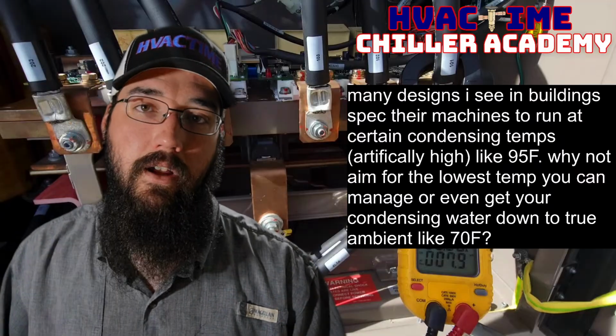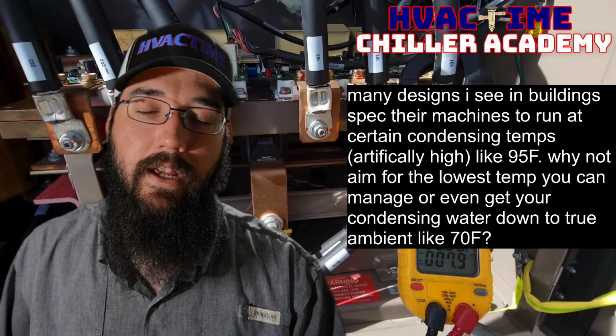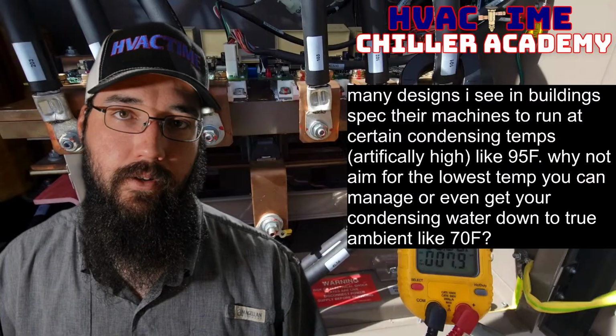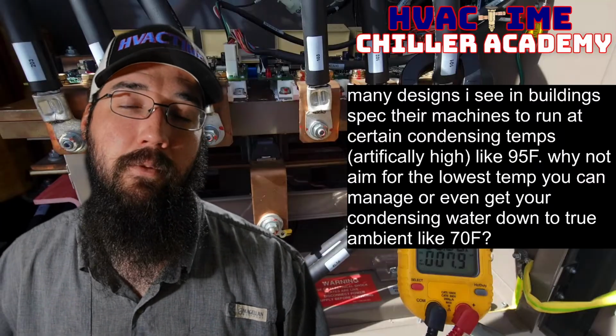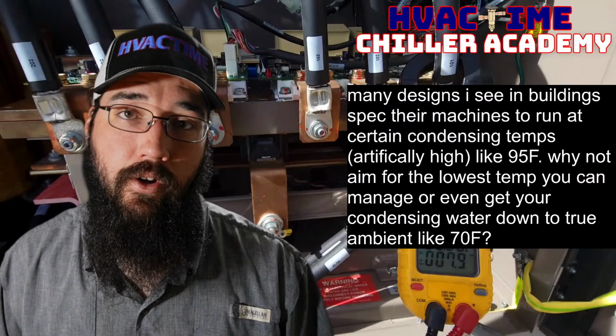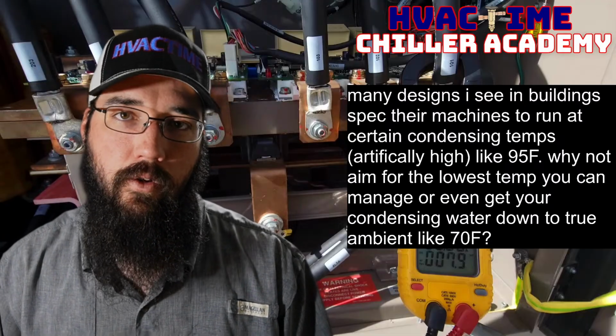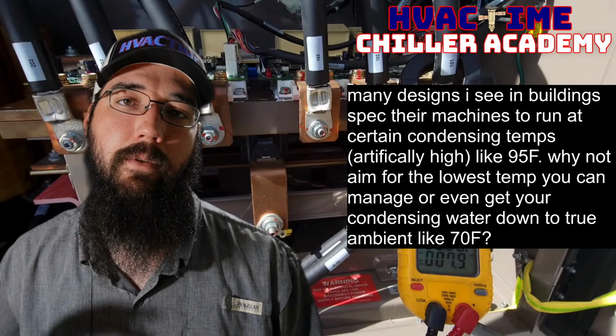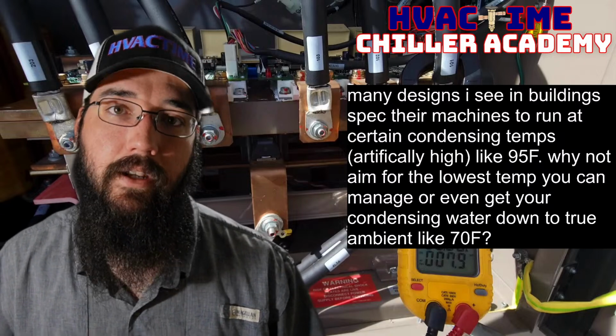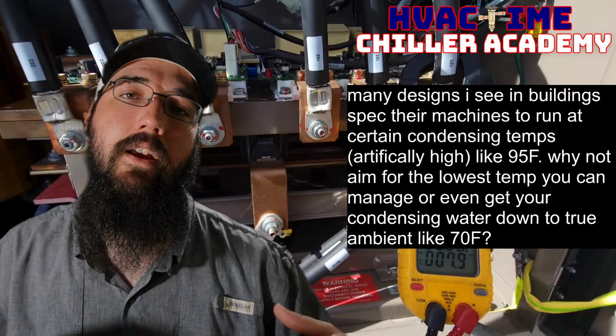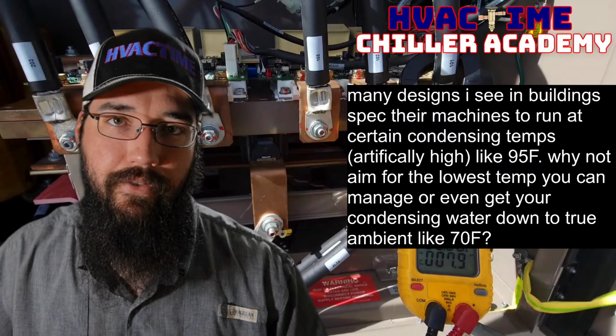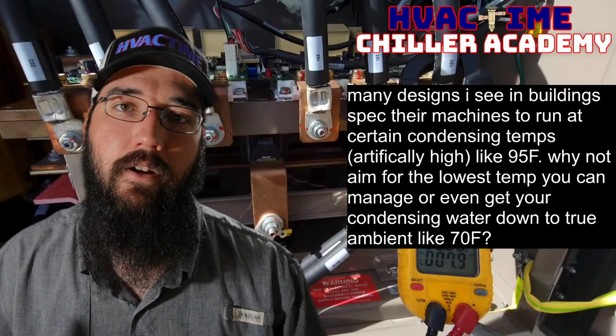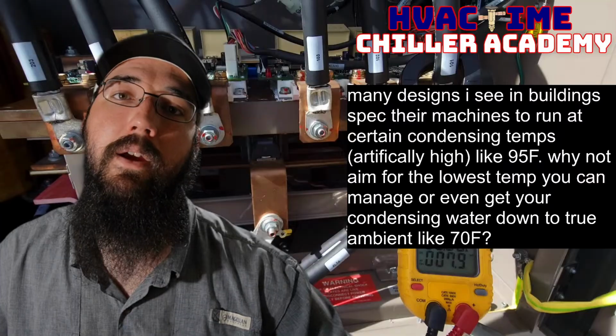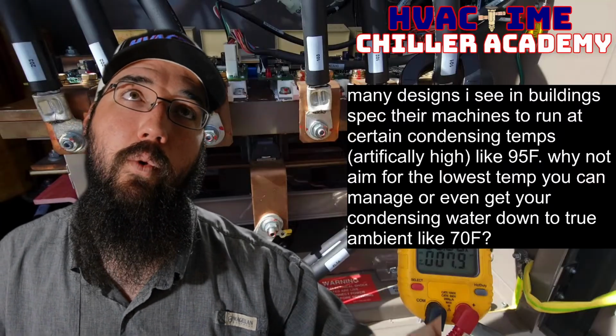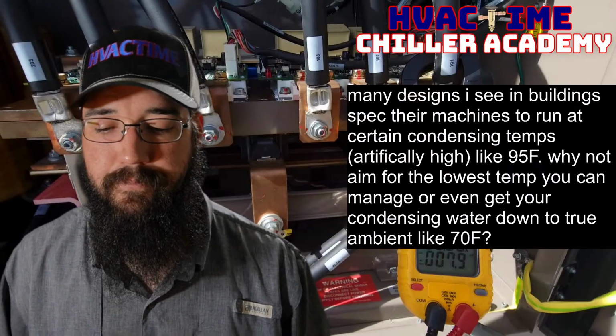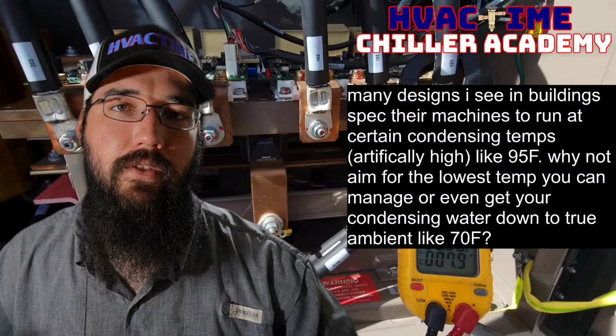So with a lot of chillers like your RTHD or a CVH, CDH, those cannot operate with cold condenser waters. They need that warmer water to maintain proper oil return, because part of what happens is if we drop that condenser water too low, the eductor system can't recover the oil back properly because we're using hot gas off the condenser to feed the eductor circuit. So if we do not have enough velocity on that hot gas, then we cannot properly create the Venturi effect, the siphoning effect, to draw that oil-laden refrigerant back off of our evaporators, which then allows it to stack up. Or if we have a gas pump, being able to properly push that oil-laden refrigerant back up into the compressor, an RTHD example. So that's the consequence of getting too low.